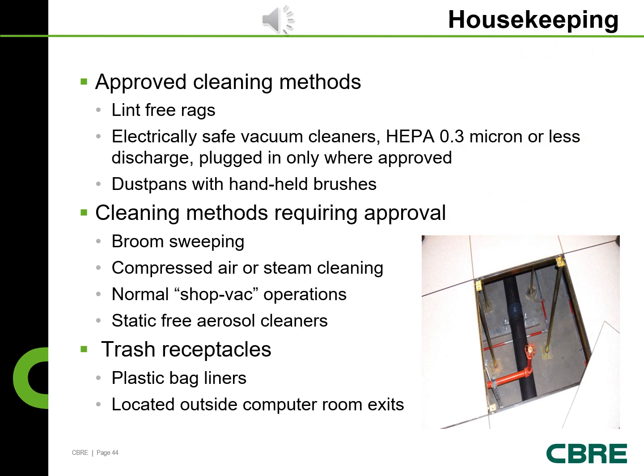Approved cleaning methods. Lint-free rags, electrically safe vacuum cleaners, HEPA 0.3 micron or less, discharge, plugged in only where approved. Dustpans with handheld brushes. Cleaning methods that require approval. Broom sweeping, compressed air or steam cleaning, normal shop vac operations, static-free aerosol cleaners. Trash receptacles have plastic bag liners and are located outside computer room exits.